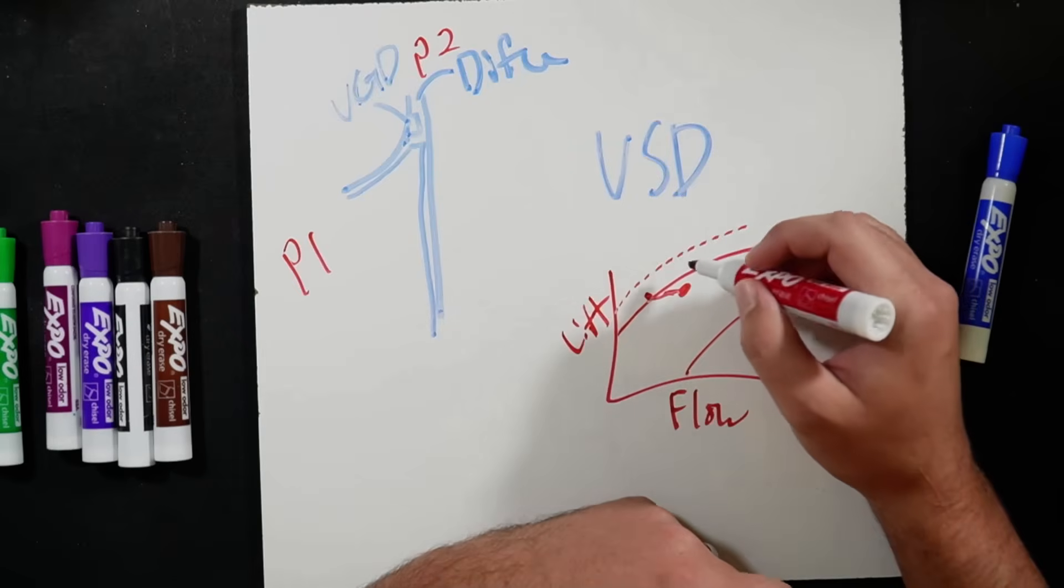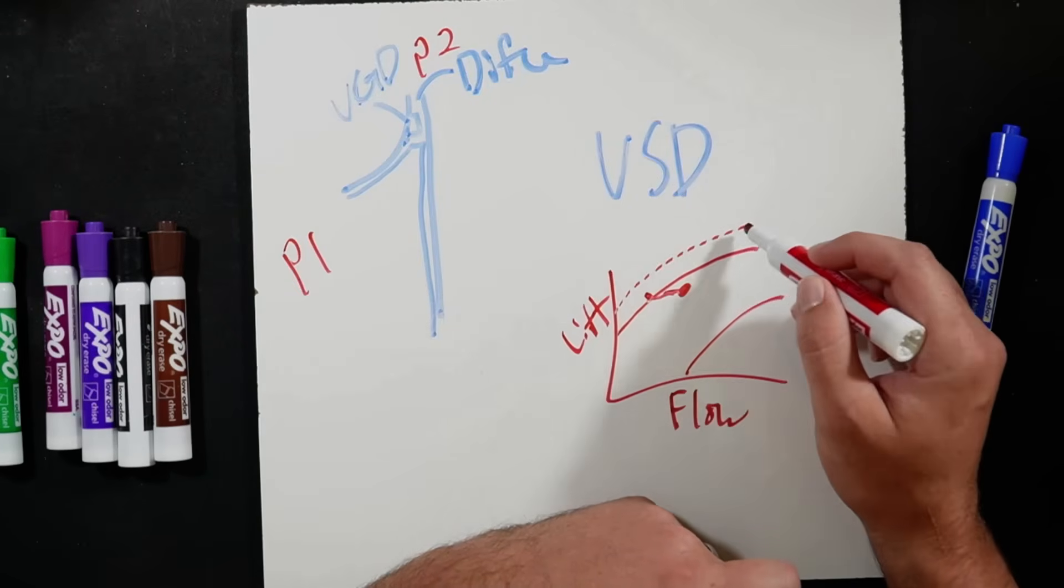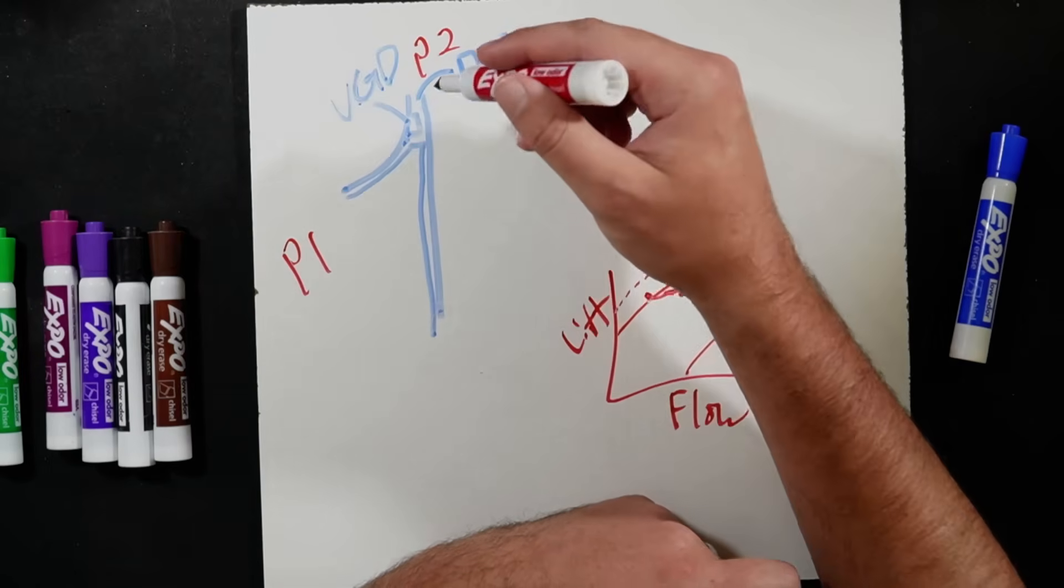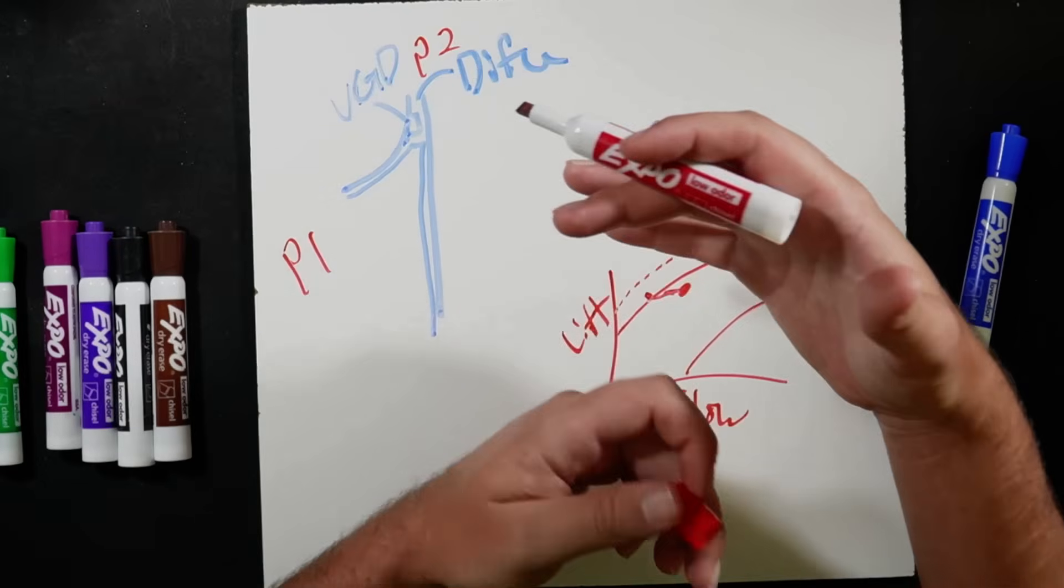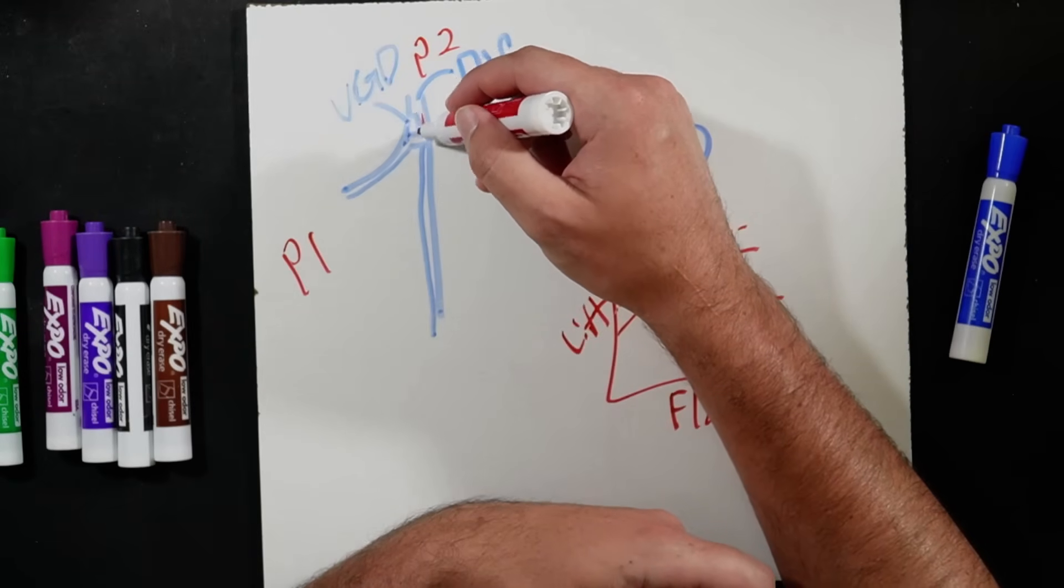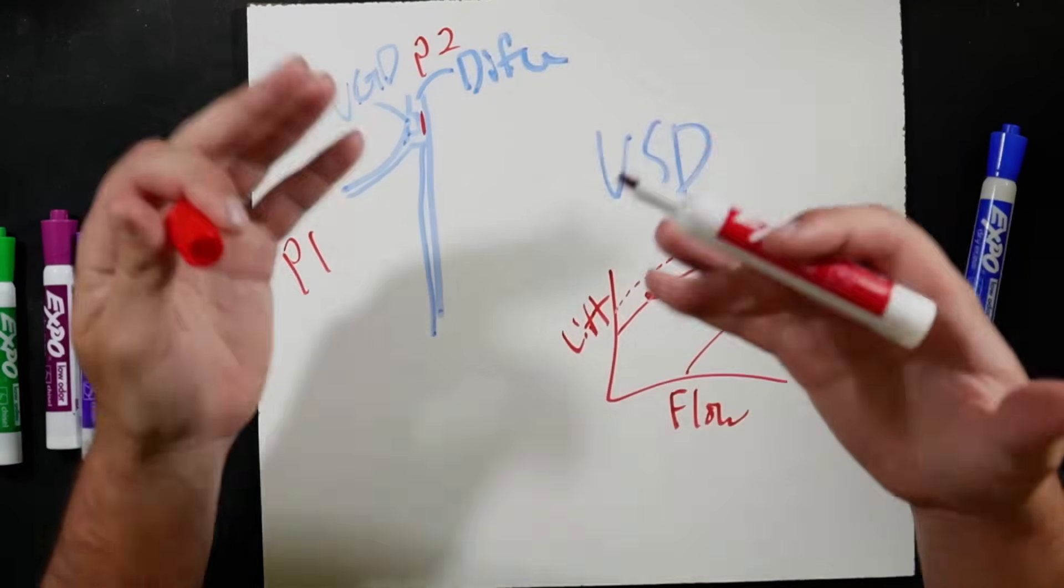Now the other thing is we do reduce flow. So part of that VGD is it does cut down on how much flow is able to go through that diffusion gap because it does become a physical block. And so our little gap here that we can flow through in the diffuser does become smaller.